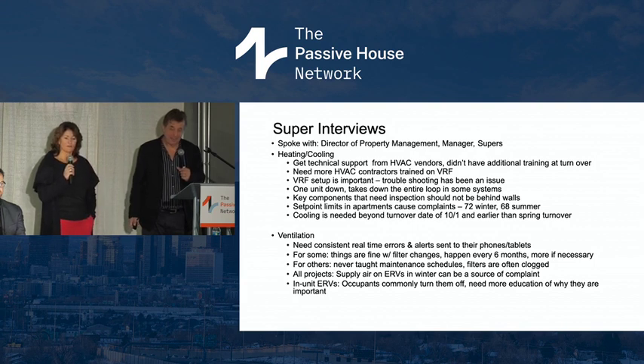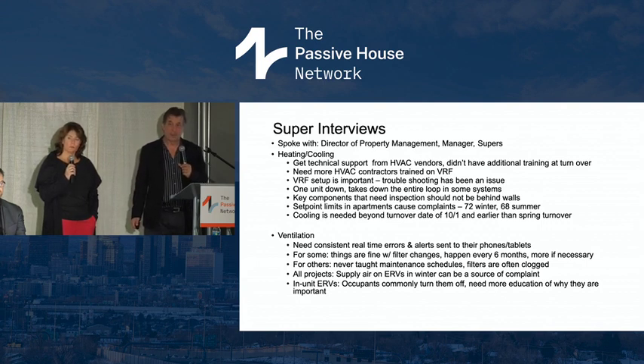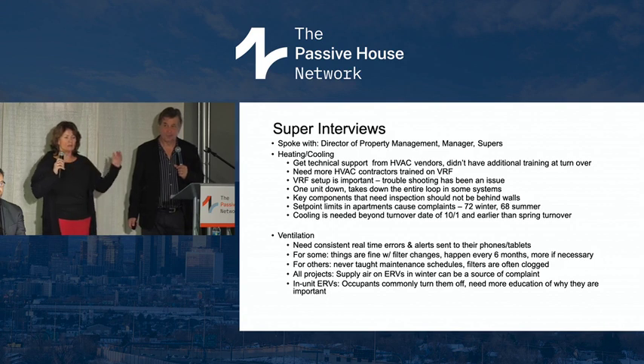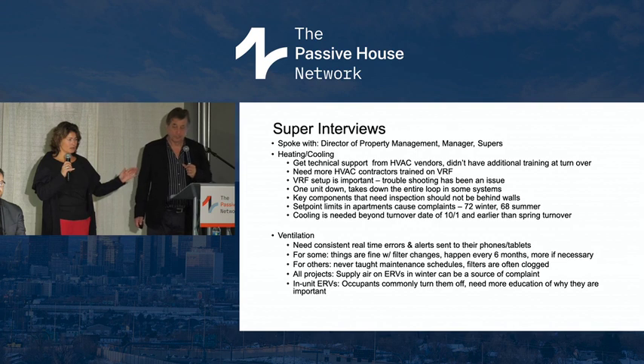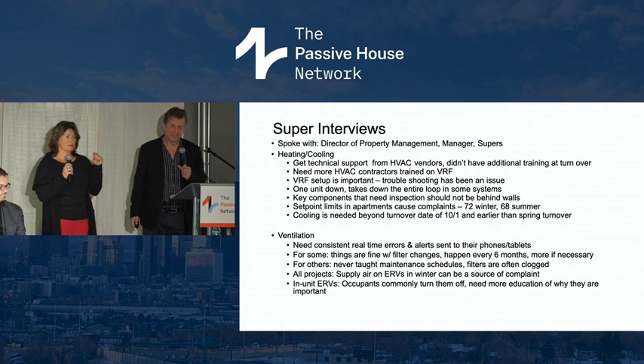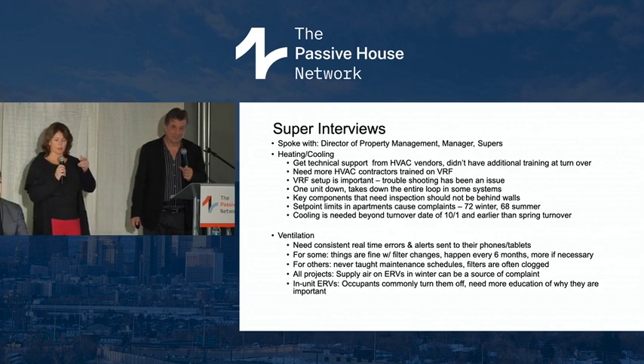Cooling is needed beyond the traditional turnover date. You don't use more cooling in a passive house project overall—I want to make that clear. Your peaks are lower, but you need it for longer. So overall it's not going to add up to more cooling than a traditional building, but you can't just shut it off October 1st—it was 84 degrees October 2nd in New York. If they turn these systems over, they're going to get everyone complaining. So you have to know your building and how it responds to the outdoor temperature.